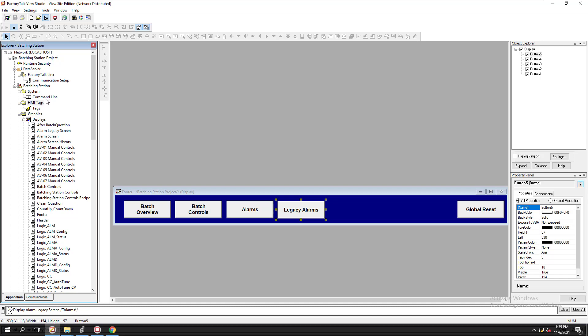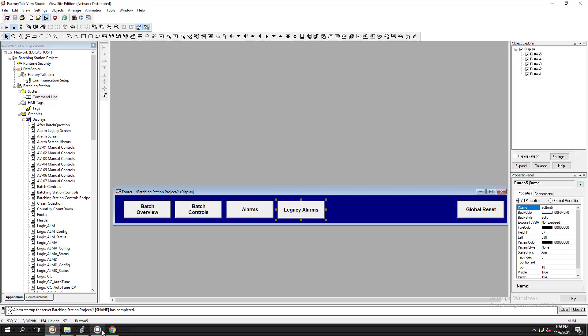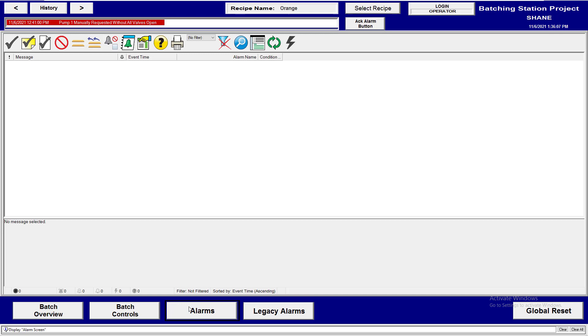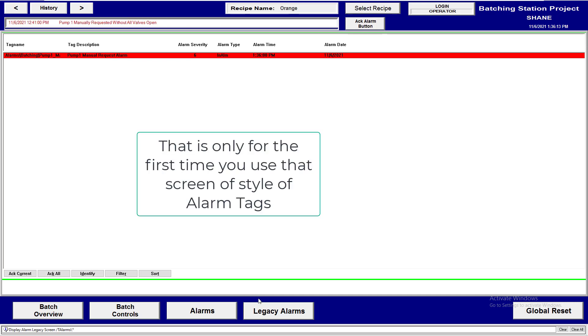If you're deploying a new system and your alarms are not showing up, come over to the command line and type 'alarm off' and hit Enter, then type 'alarm on' and hit Enter again. That will actually help trigger the alarm screen to work, because sometimes when you first deploy the screen it may not trigger or work correctly.